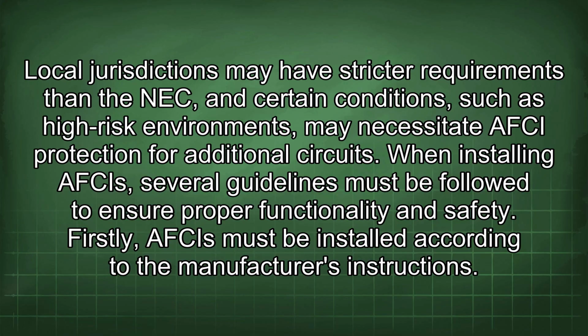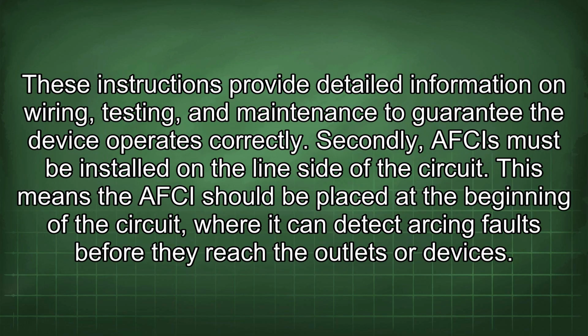Firstly, AFCIs must be installed according to the manufacturer's instructions. These instructions provide detailed information on wiring, testing, and maintenance to guarantee the device operates correctly. Secondly, AFCIs must be installed on the line side of the circuit. This means the AFCI should be placed at the beginning of the circuit, where it can detect arcing faults before they reach the outlets or devices.